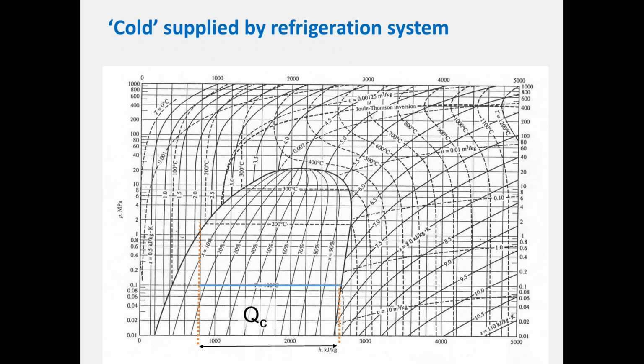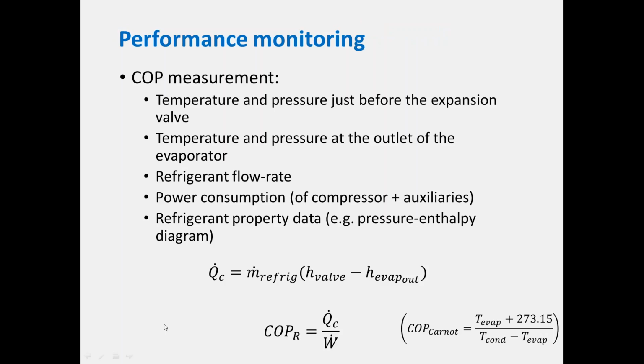So I've got a pressure enthalpy chart here. So the two points I was talking about, if you have it just upstream from the expansion valve, all you need is temperature and pressure, and this point is fixed. And then you can draw that down to the bottom, work out the enthalpy, and then just at the suction point for the compressor, work out the enthalpy there. The difference between those two enthalpies multiplied by the flow rate of refrigerant will give you the cooling capacity, and if you've got the power drawn by the compressor plus auxiliaries, you can get an estimate of the efficiency of your system.